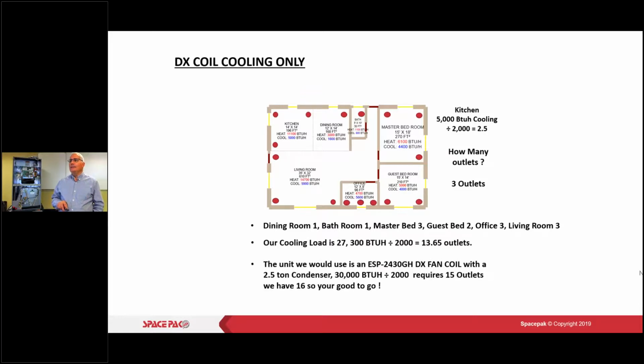So the cooling load's 27,300. That would be 13.65 outlets, that's going to be 14. So we use a 2430 with the DX coil, 2.5 ton condenser, 30,000 BTUs requires 15 outlets. So if you have 16, you're good to go. Any questions on that? I have one.